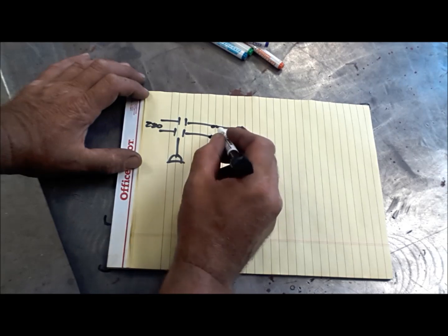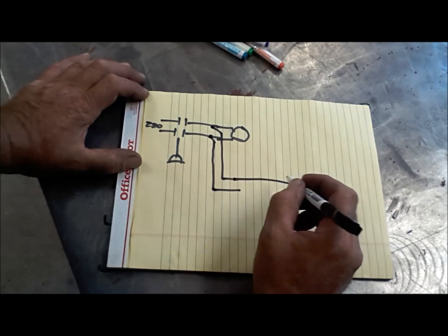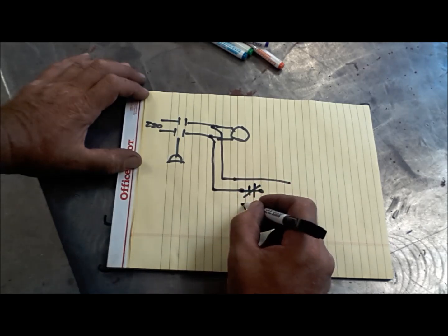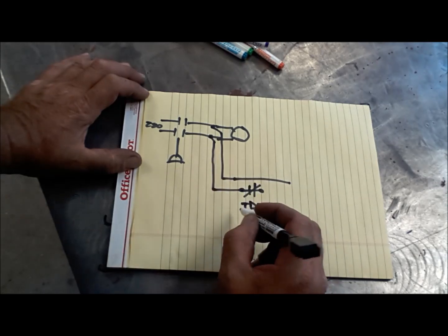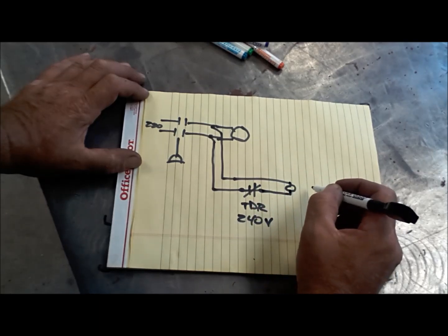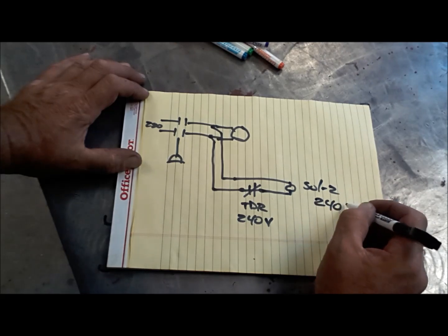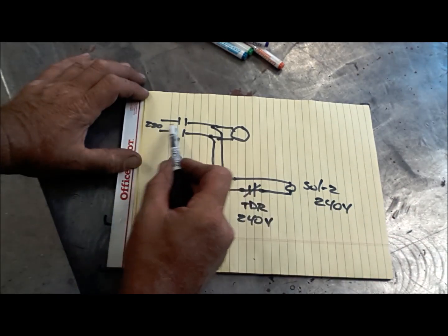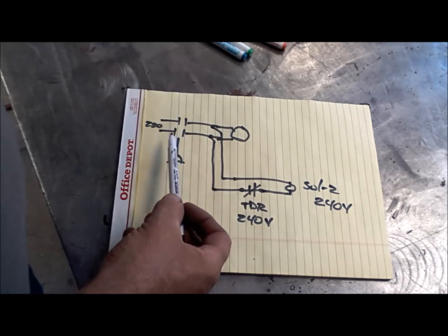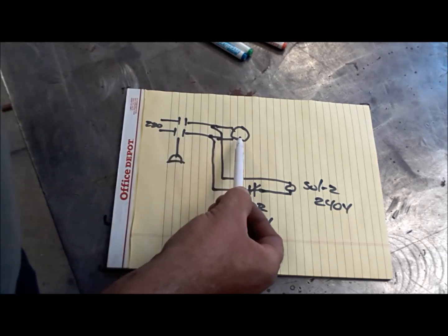So off of here, you're going to come down and break off of here and break off of here. And your TDR is still going to go in line and that's still going to be a normally closed. You have to get one that, you have to get your TDR has to be rated for 240 volt and your drain solenoid, which is a solenoid, we call it solenoid two. Solenoid two also has to be rated 240 volt. So you would need to get both high voltage. So you're running full line voltage for everything on this. This is not like a motor starter application. And this is how a lot of OEMs do it is with a kind of a manual pressure switch that opens and closes two separate poles and turns the motor off and on directly.